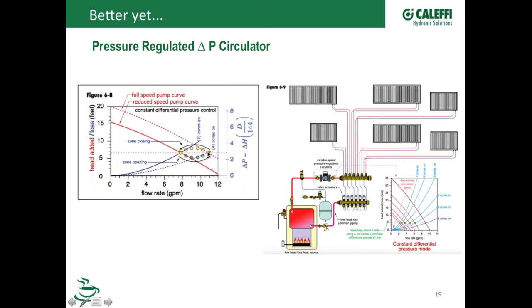So again, we started out with a peak demand of maybe 11 gallons per minute when all the zones are open. And as the zone valves close, you can see that we're not running up this pump curve. We're keeping that pretty flat. And we're doing it instead of slipping the clutch at the pressure bypass valve. We're just telling the circulator, slow down, I don't have as much work to do. Ramp it down. That's handled internally with this pump, which has that logic built right into the processor on these delta P pumps that know when this condition is happening, when these valves start shutting off, and they just ramp this curve down and automatically adjust to the system.